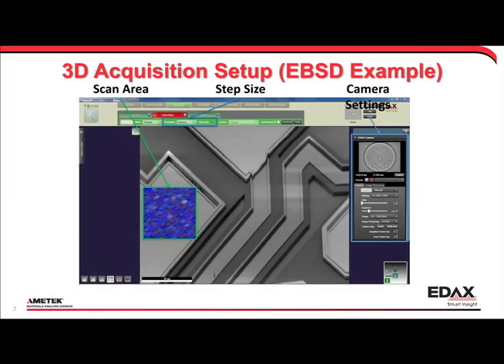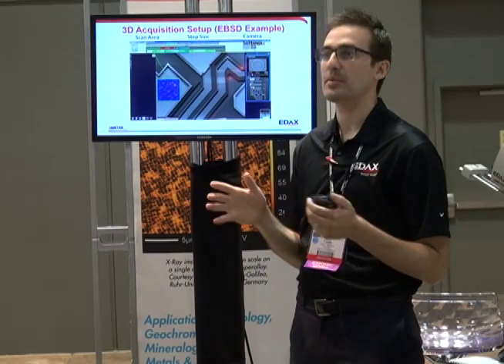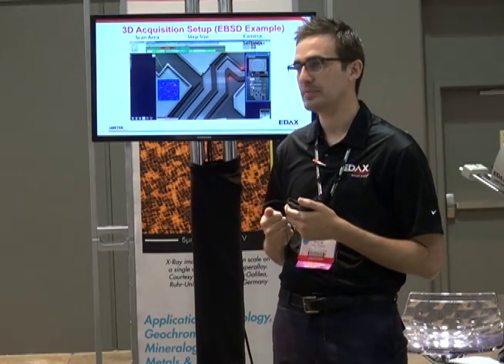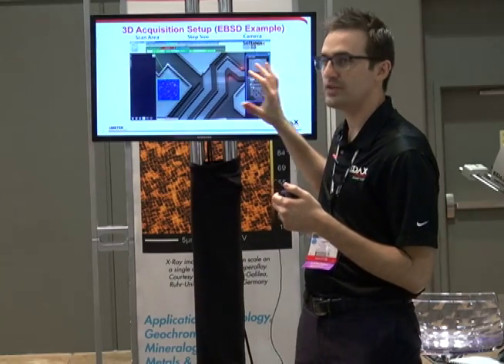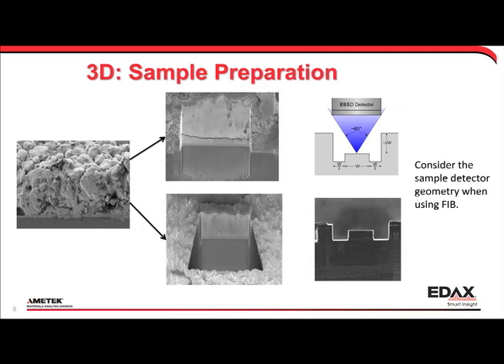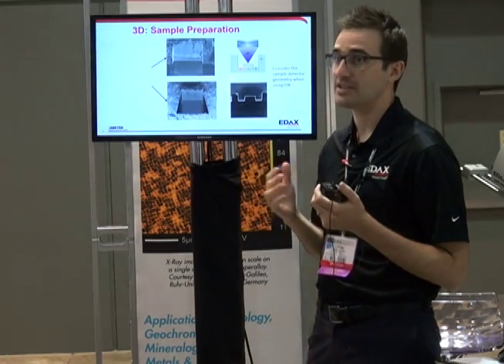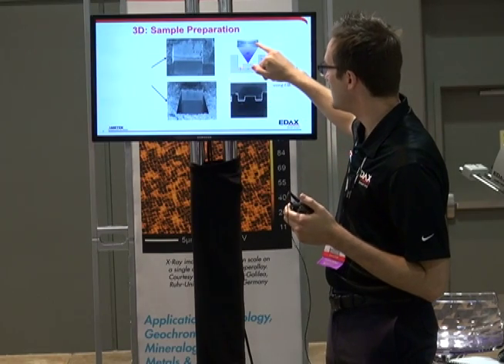With the TEAM software, this is the gist of 3D acquisition. There'll be some kind of wizard or outside application for acquisition, and you'll be taken into TEAM where you set up the scan parameters. What I've shown here is EBSD since that's my forte, but the same applies for EDS — you go in, set up your scan resolution, any detector parameters you need, such as your amp times, dwell time, and frames per level. If you've used TEAM, doing the 3D step is not a quantum leap.